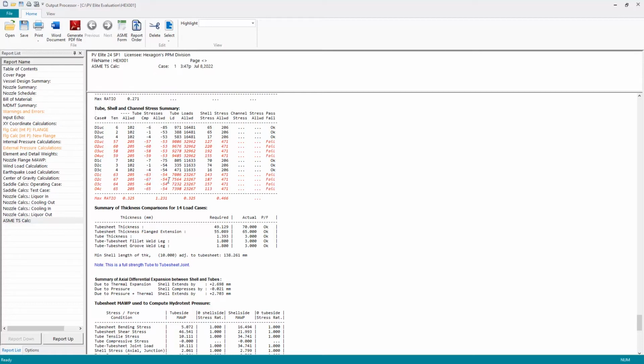This, of course, being due to the thermal expansion differential between the tubes and the shell. They're expanding at different rates, of course, they're different materials, and of course, different temperatures. So we have an issue with compression, we have buckling problems, essentially, with our tubes.